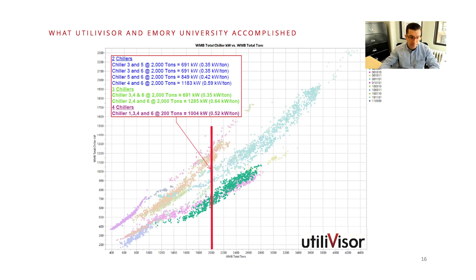And this is kind of off topic, but sometimes a lot of people feel as though, if I put a VFD on something, I'm going to save energy. And common engineering theory is, I'm going to run all of them at part load conditions. But there's even a break point with that, where sometimes scaling back and reducing the quantity of equipment on drives is more cost effective. This was just an example from the holistic standpoint.